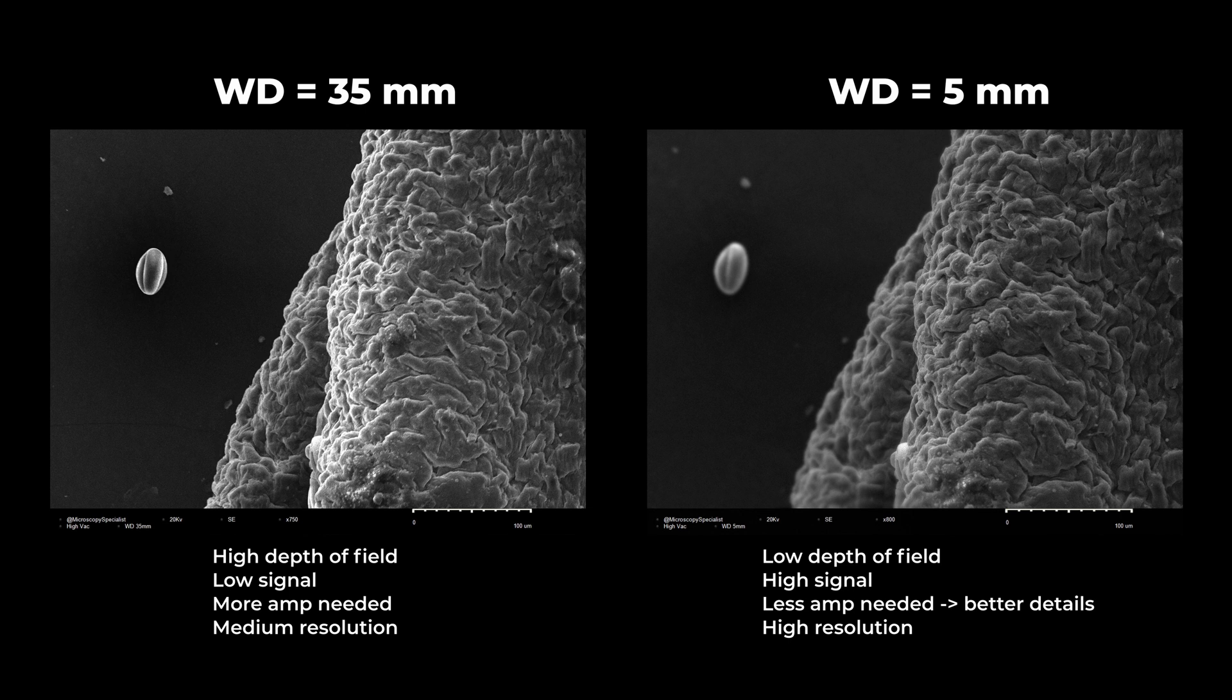As for the resolution, it decreases since the electron beam which travels a long distance will focus worse due to aberrations and environmental influences. Secondary electron collection and signal-to-noise ratio are also reduced. If you want to get the maximum resolution, be sure to check the manual of your microscope. Every microscope has an optimal working distance for high res images on high magnifications.